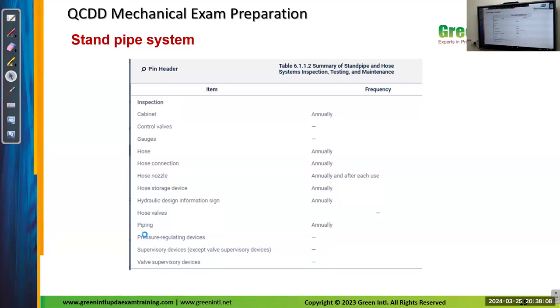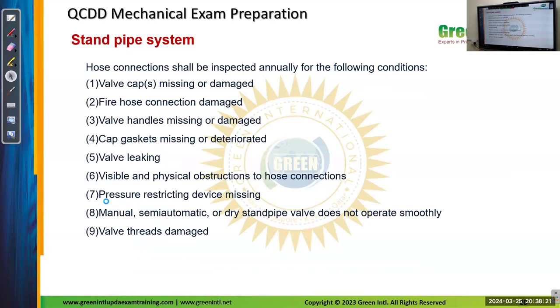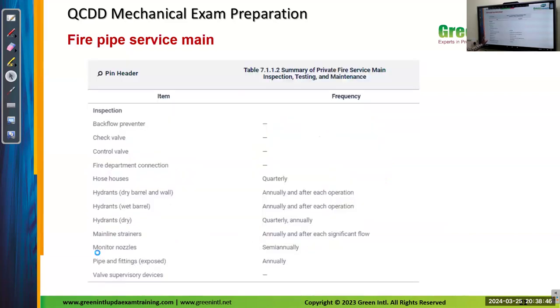This is for inspection, testing, and maintenance for standpipe and hose systems. Various components of inspection and their frequency are given. Similarly, testing is also given. So hose connections shall be inspected annually for the following conditions: valve caps missing or not, fire hose connections damaged, handles missing, cap gasket, valve leaking, visible and physical obstructions, pressure restriction devices, manual or semi-automatic and dry standpipe systems, and thread damage. If there is any damage among these, you have to undergo replacement.